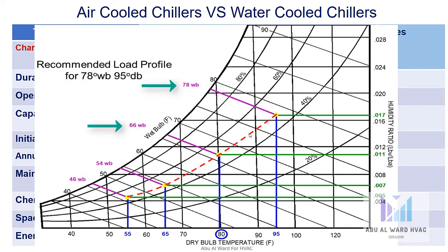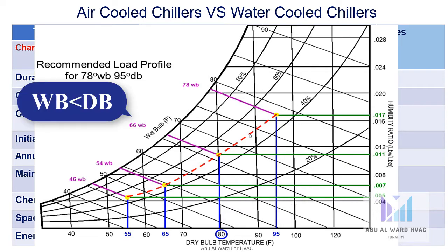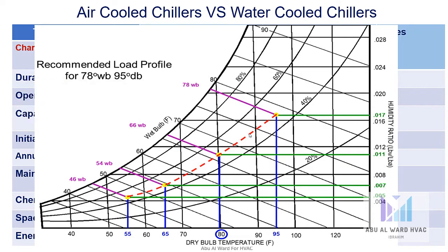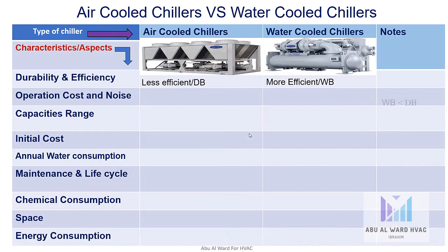According to this diagram, we can see easily that for any temperature, the wet bulb is less than the dry bulb. That's why the condenser is going to cool more in the water-cooled chiller. That's why it is more efficient than air-cooled chillers. Operation cost and noise. The air-cooled chillers are more noisy because they have big fans to cool the condenser, and they have more operation cost, while the water-cooled chillers are less noisy and have less operation cost.